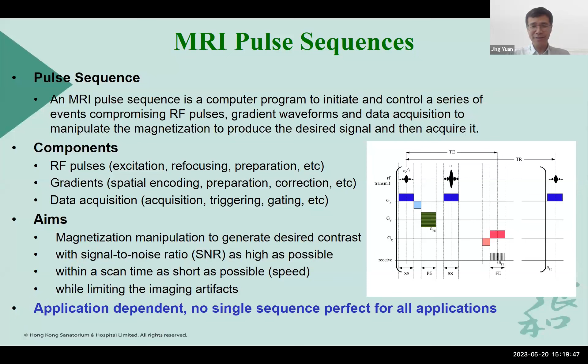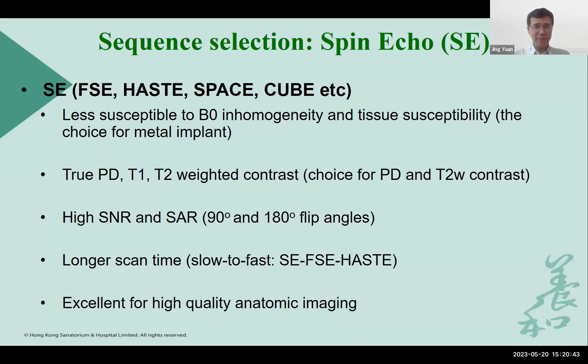They are both associated with many derivatives and have different vendor names. These two sequences have different characteristics, so they are used for different scan tasks. For example, the spin echo pulse sequences have a higher signal-to-noise ratio and are less susceptible to B0 inhomogeneity, but usually have slow scan speed and high specific absorption rates. They are excellent for high-quality anatomic imaging. So they are frequently used for MR-guided radiotherapy.